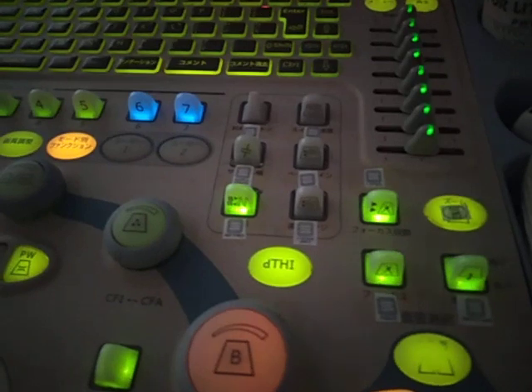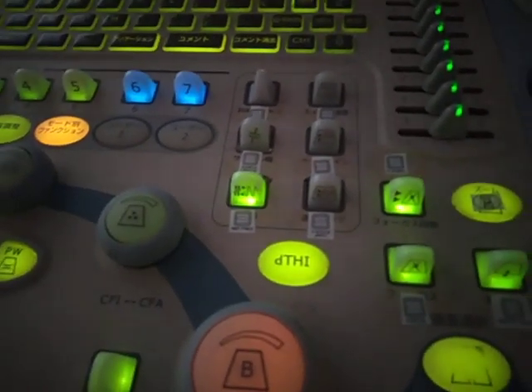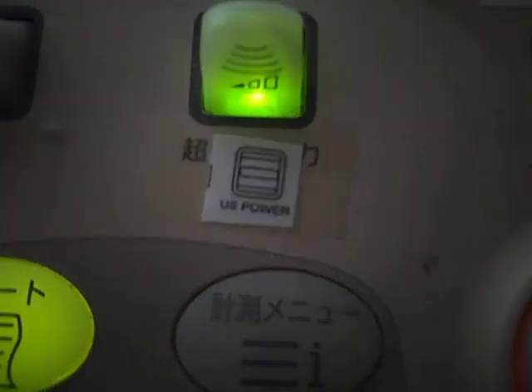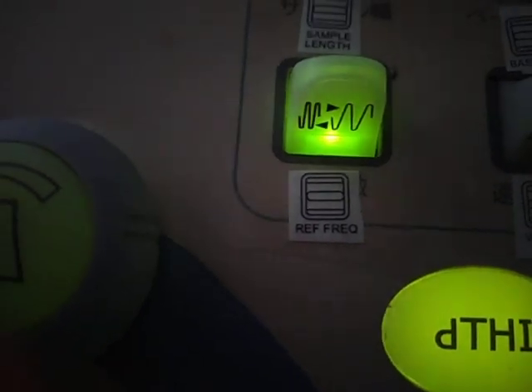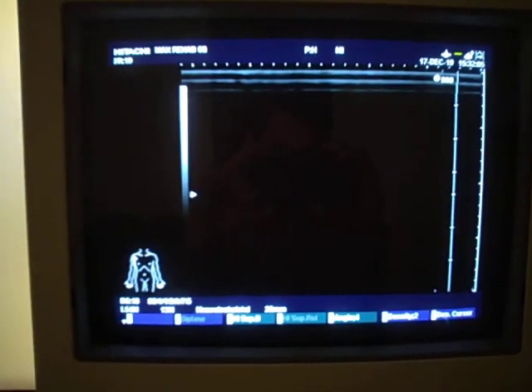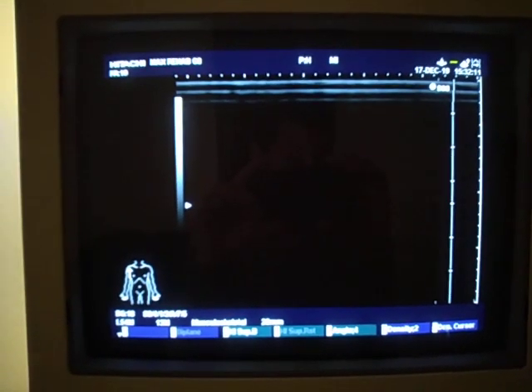And the fourth one that we need to know about is the frequency. So always try to adjust the frequency. For example, this is ultrasound power in my unit. There you go. So that is ultrasound power. In most of the units you might not have this, but you have what is called the reference frequency. So that is ultrasound frequency, the working frequency. With higher frequencies you are getting a very good image, but with lower frequencies you are getting a deeper image, a deeper depth. So let's start with how the modes appear.